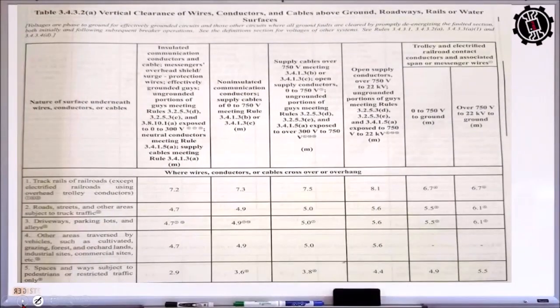Yan. So this is now the table sinasabi ko kanina, no? So makakuha niyo ng copy nito when this whole presentation will be printed, no, or will be converted into PDF, no? So we have here the nature of the conductors, and this is table 3.4.3.2(a), the vertical clearance of wires, conductors, and cable above ground. No? So yung ground ito is yung sa lupa, roadways, rails, or water surfaces. So this is insulated communication conductors and messengers. So they are effectively grounded. So ito yung mga nakasuntaan na rules. So yung mga all about communication cable na discuss natin kanina. Ang rating is 0 to 300 volts. So ito yung susundin na mga clearances. So these are all in meters.